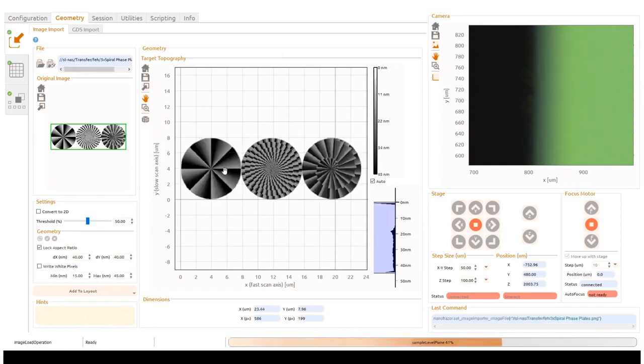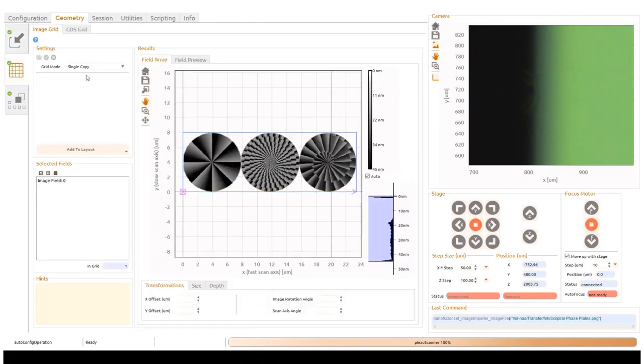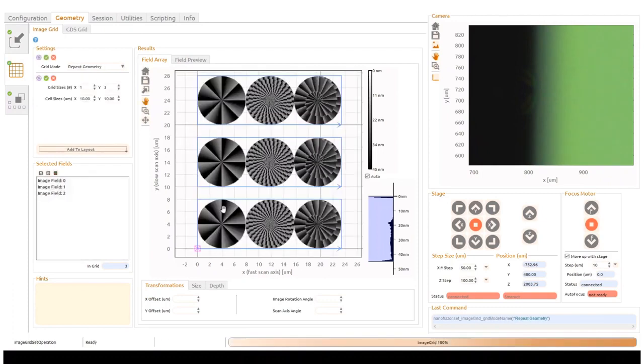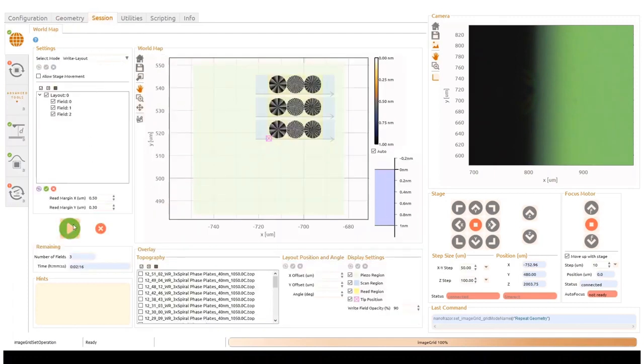Maybe approach is one of the common ones. But while it's doing these calibrations, we start loading already our layout. So we take these spiral phase plates, different gray values, and pixel size is now here 40 nanometer. They will be patterned between 15 and 45 nanometer deep. We can go here and actually repeat this field multiple times. We just select here, repeating this field 3 times.